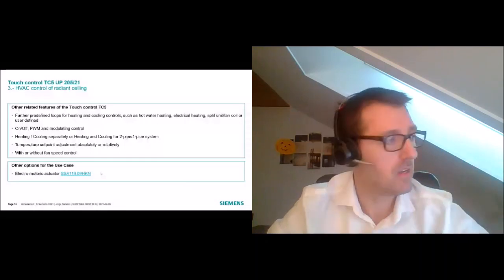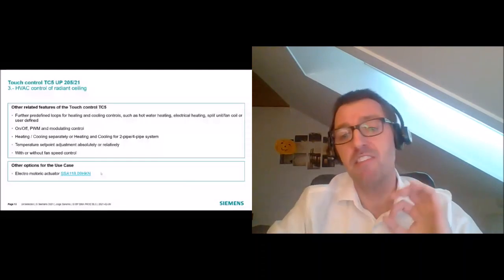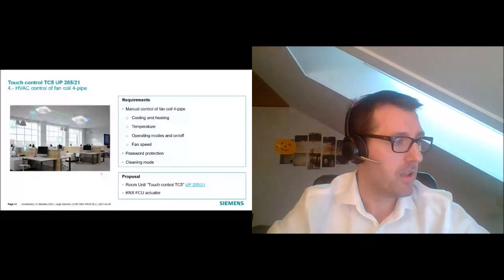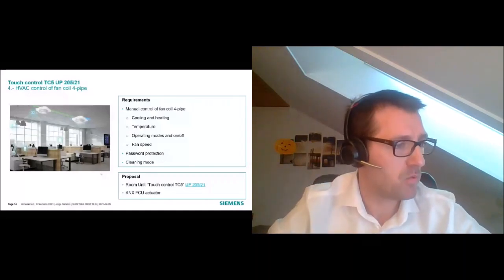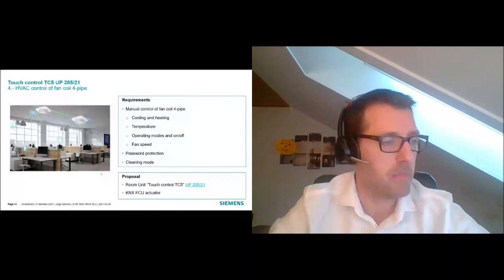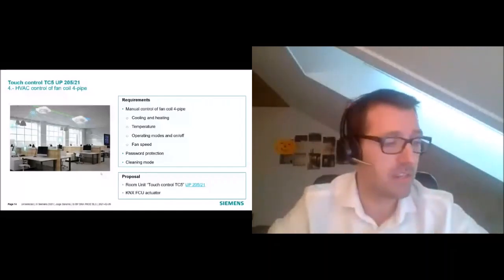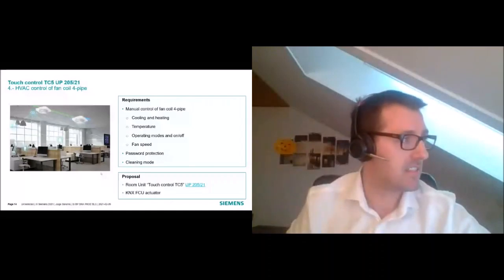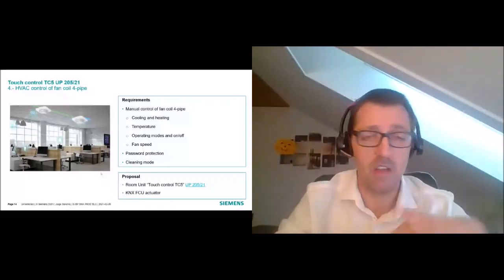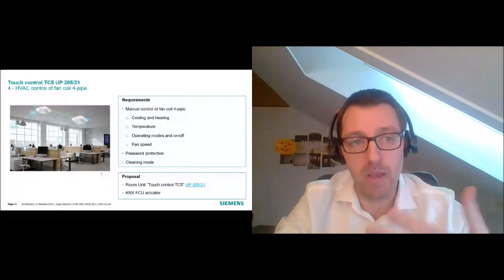Use Case 2: the same room but now with a fan coil. Requirements are similar as before, but now we include fan speed control. The customer also wants to protect the TC5 settings page with a password, and a cleaning mode is needed. Proposal: TC5 and a KNX fan coil controller. For the solution, we again configure the thermostat in the TC5 — the only difference is we also enable fan speed, and in the predefined loops it's recommended to select Fan Coil, which provides optimized settings for this control.